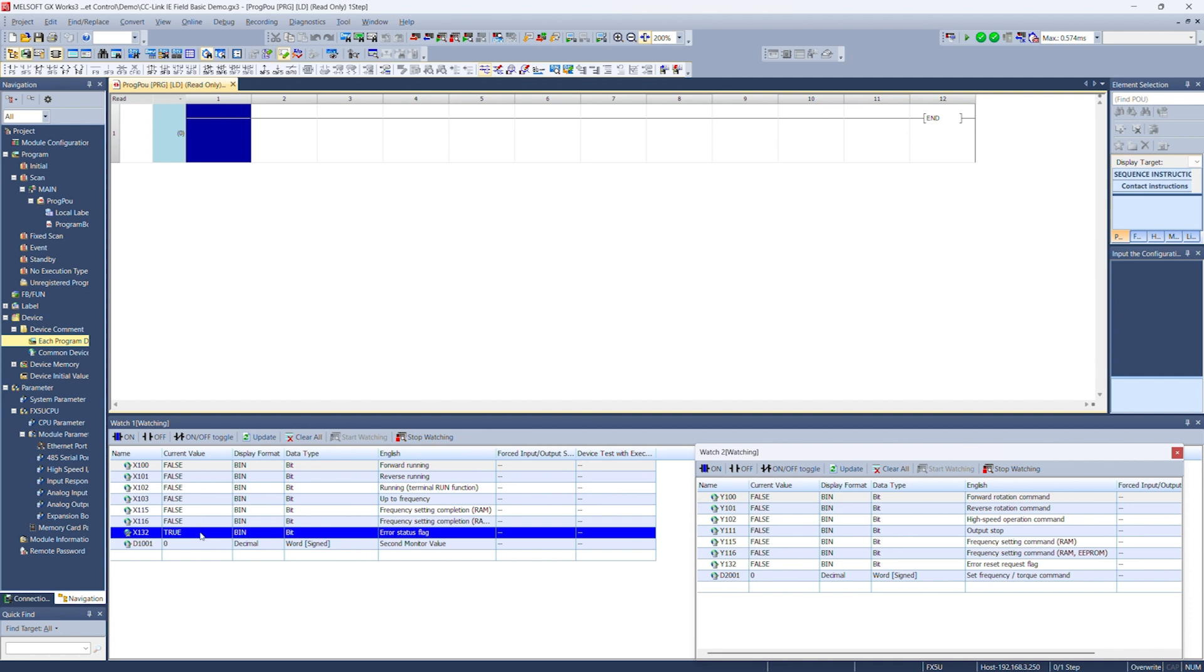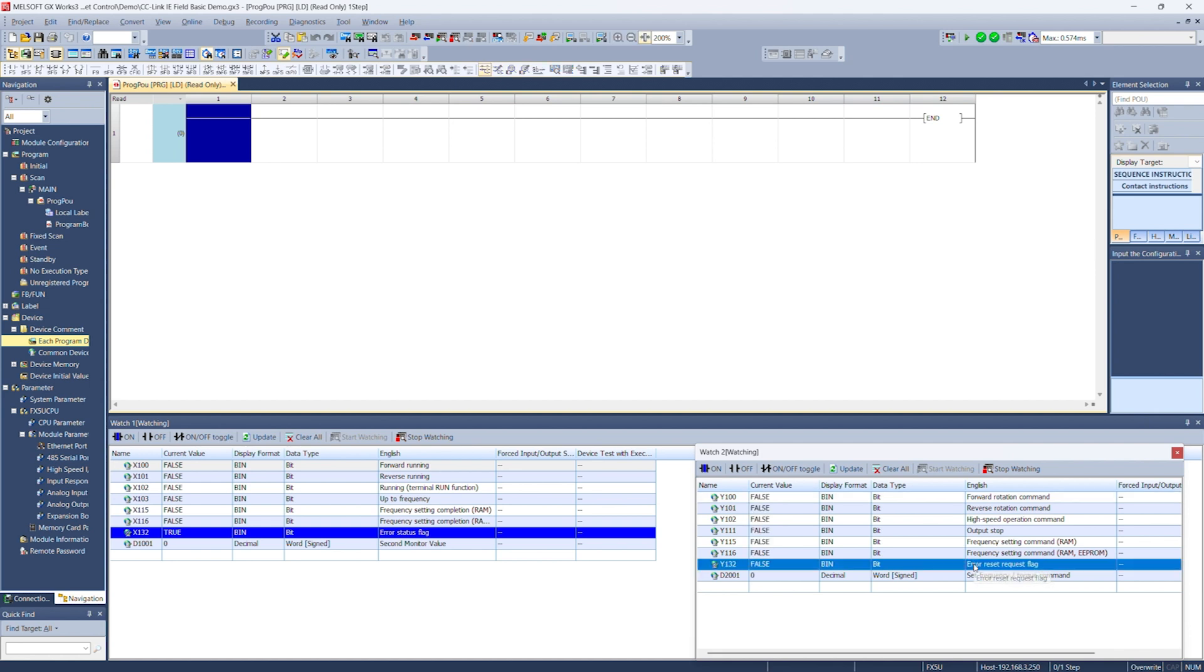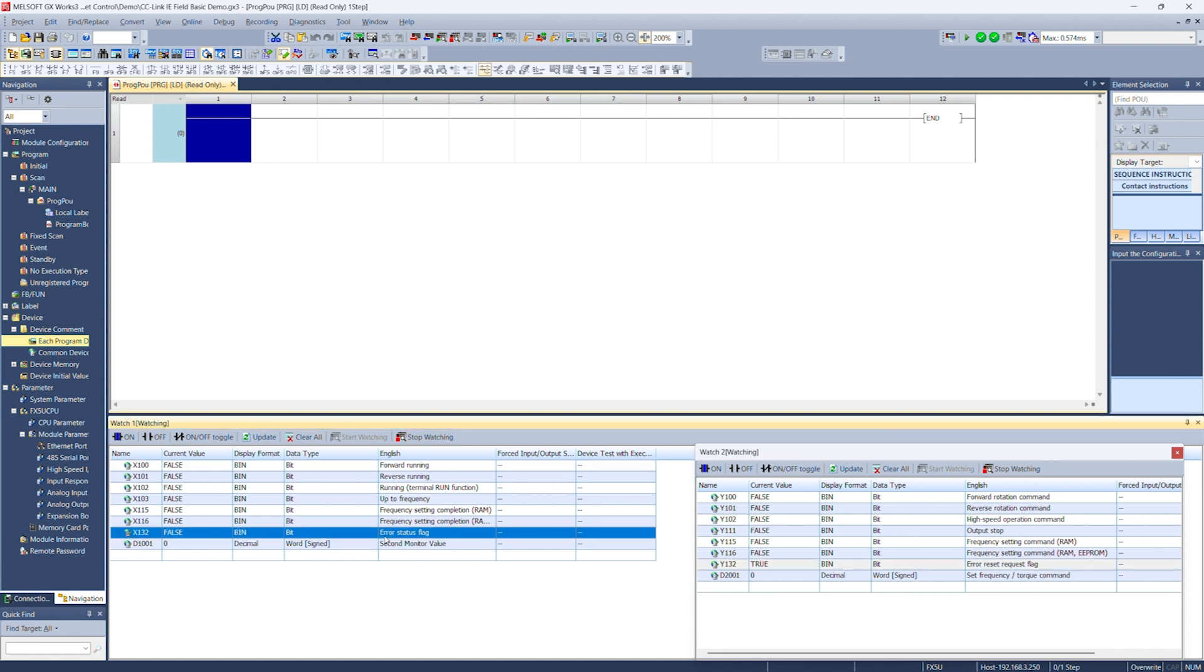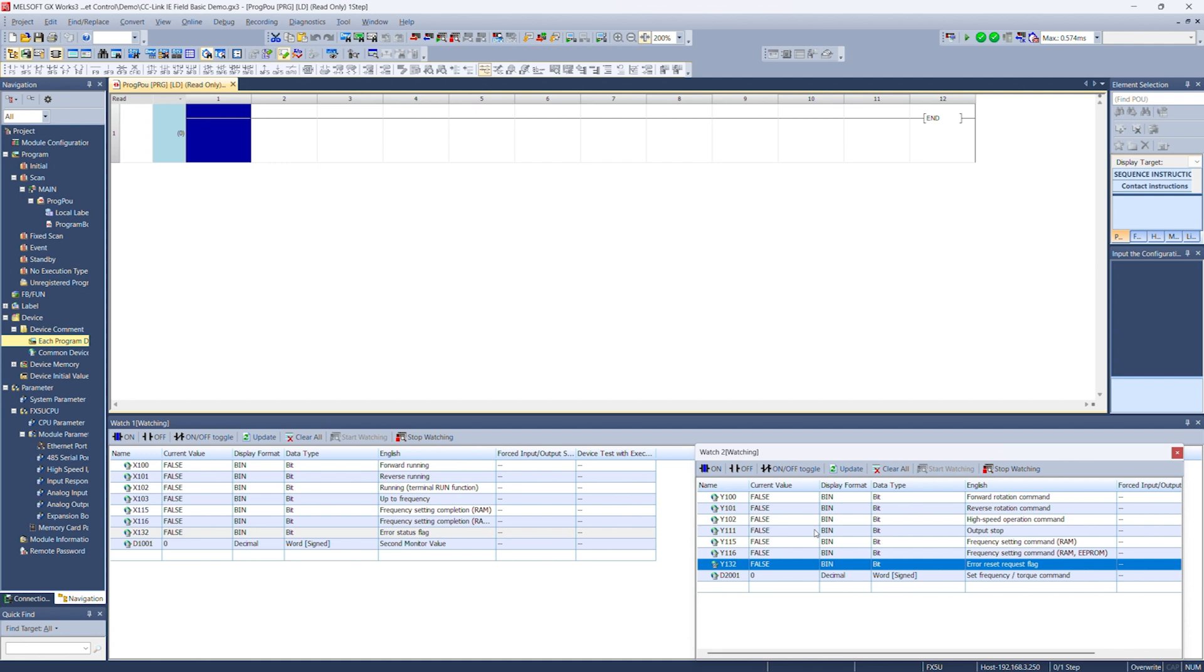So we have currently input 132. We started at 100, so it's 132. Input 32 is the error status flag. So there is an error. And if I look over at the inverter, I can see that there's an error displayed on the monitor screen. To reset this error, we can set Y132, which is the reset request flag. So if we toggle this on, we should see the error clear. I heard the inverter click. And when I look back, there's no error. It is showing me that the speed is set at 0.